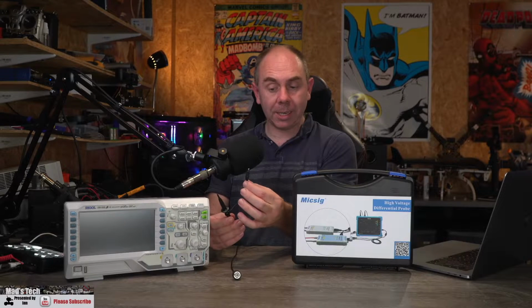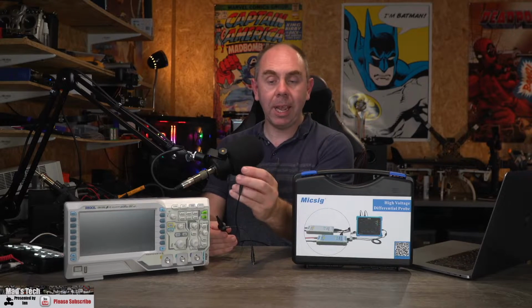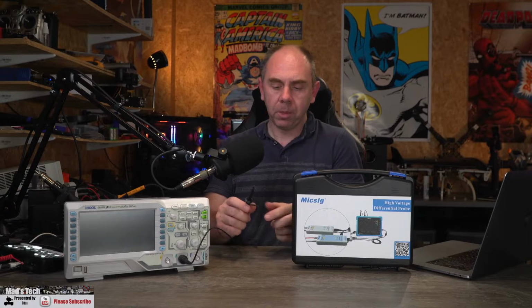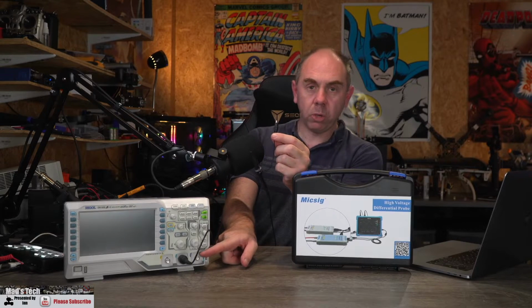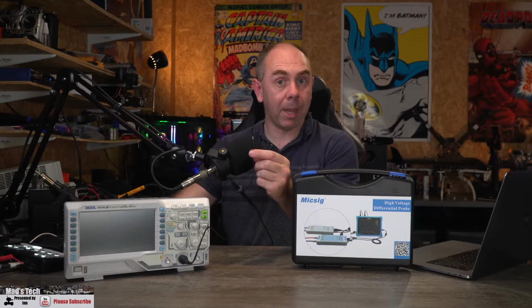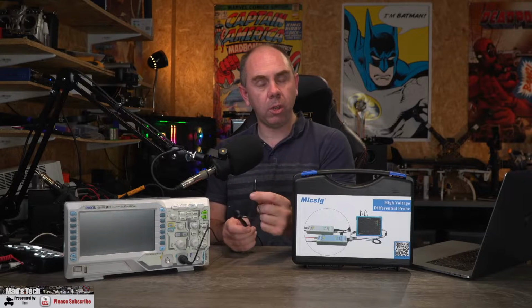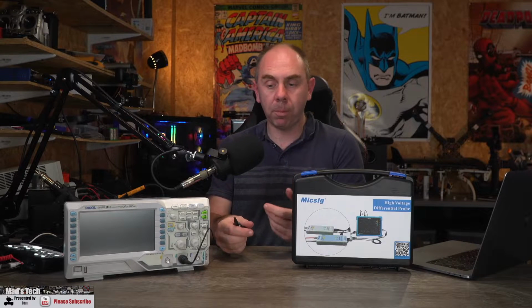The earth connector is directly connected with no circuitry all the way down the line, again to the earth connection on the probe. And when your probe is actually connected on your scope, so if I just clip it on there, this earth connector is now directly connected to all of the earth points on the front of the scope, but it's also then referenced to the earth point on the mains plug on the back of the scope. And that means anything you touch with this earth connector is referenced to the mains reference earth of your property. And when you are measuring things like DC voltages on battery devices, this really isn't a problem. However, when it comes to measuring things with AC or things that are plugged into your mains, even if it's got a mains adapter, things can get particularly dodgy, and you could have the potential of either blowing your scope up or causing yourself serious damage.